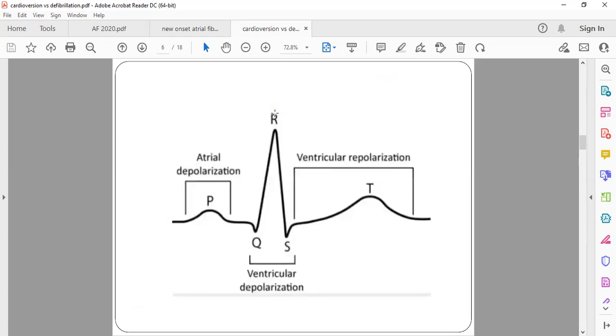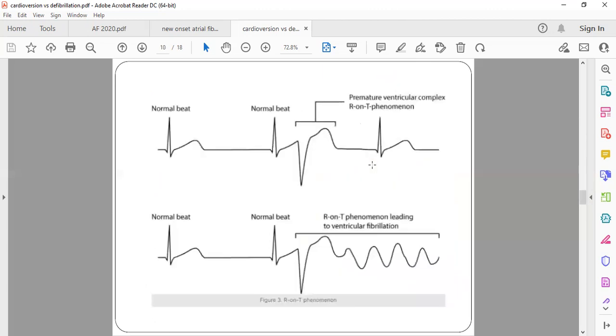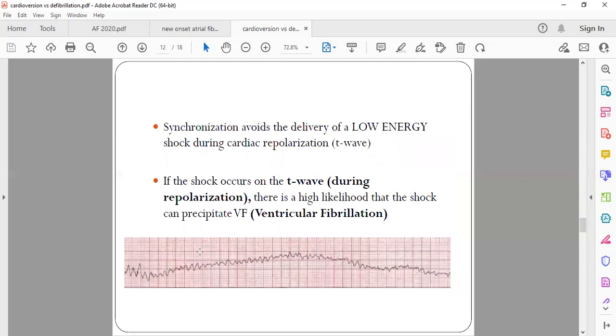Synchronization works through a sync button on the defibrillator. When you press the sync button, the machine shows marker lines over the R wave. When you place the paddles and press shock, it will not deliver immediately — it detects the R wave and delivers the shock exactly at that point, after a delay of one or two seconds. After pressing the shock button, you must keep the paddles on the chest for at least three to four seconds so that it syncs and then delivers. If you remove the paddles immediately, the shock will be delivered in the air.